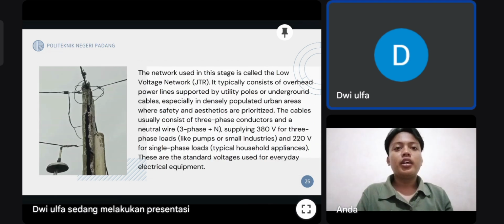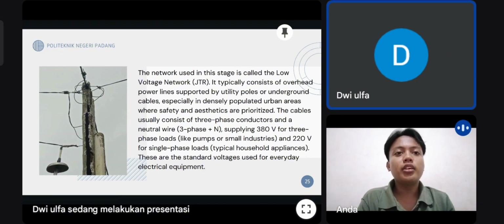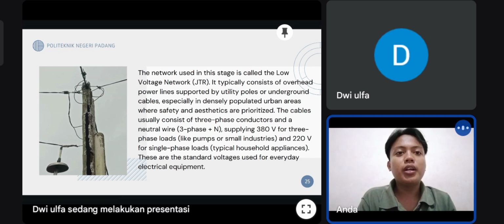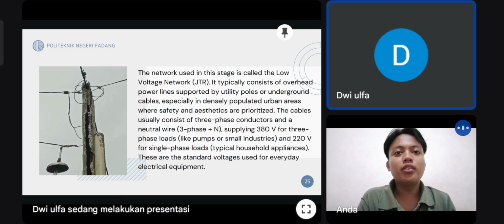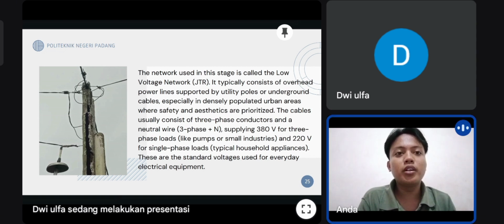The system or network used in this stage is called the low voltage network. It typically consists of overhead power lines supported by utility poles or underground cable, especially in densely populated urban areas where safety and aesthetics are prioritized. The cable uses a 3-phase conductor and neutral, supplying 380 volt for 3-phase load and 220 volt for single phase load. These are the standard voltages used for everyday electrical equipment.